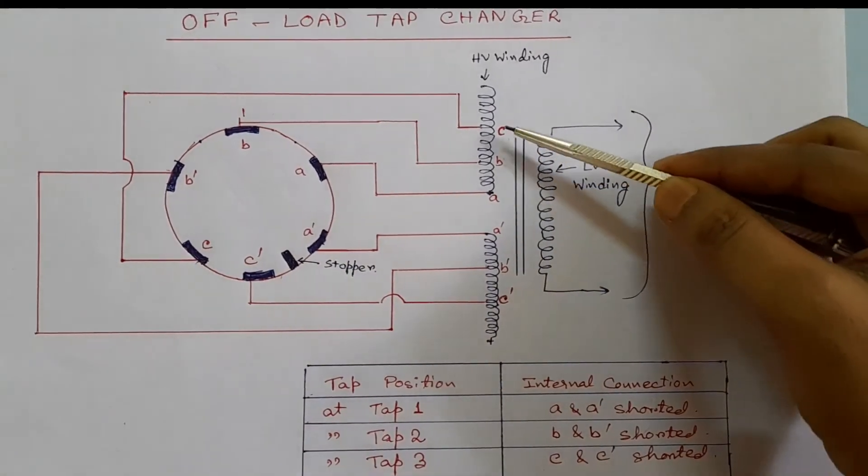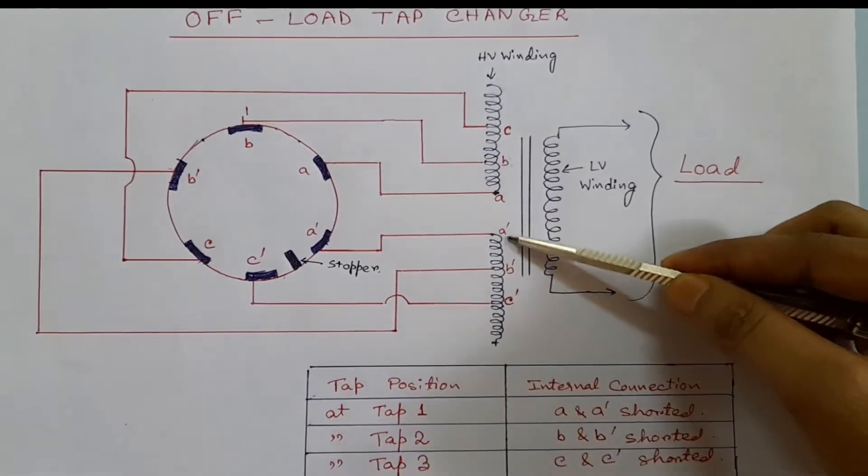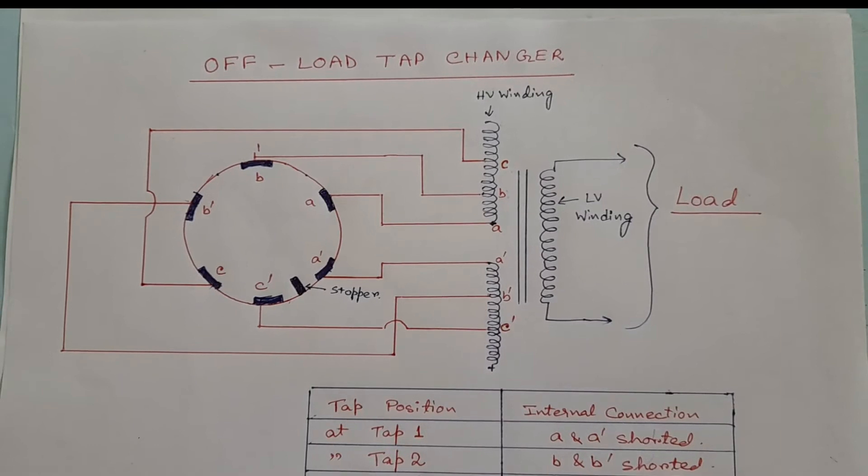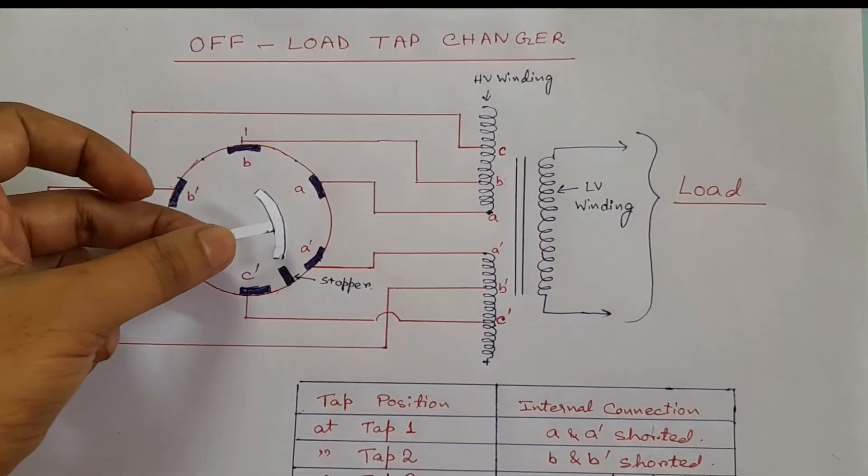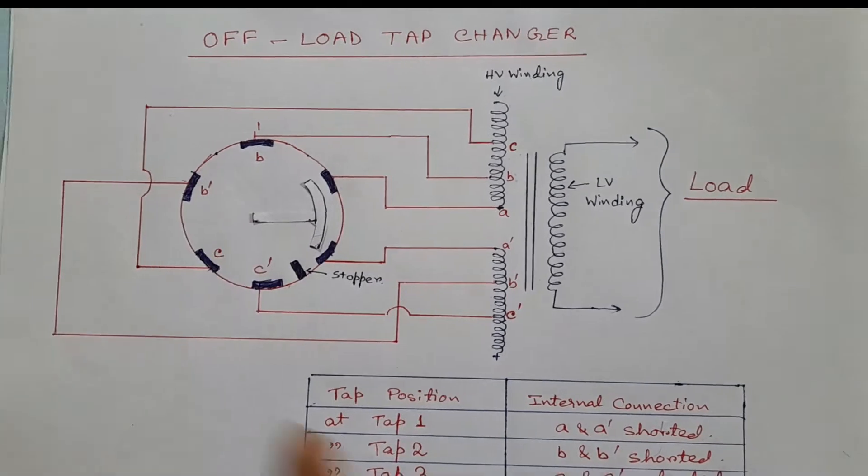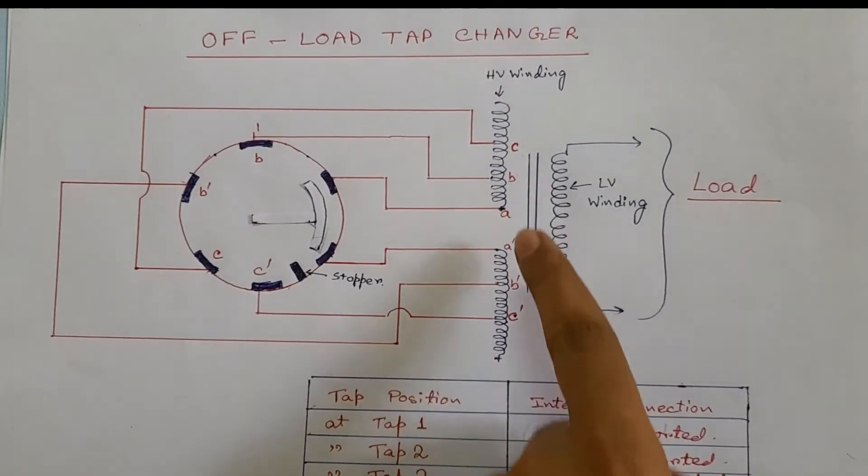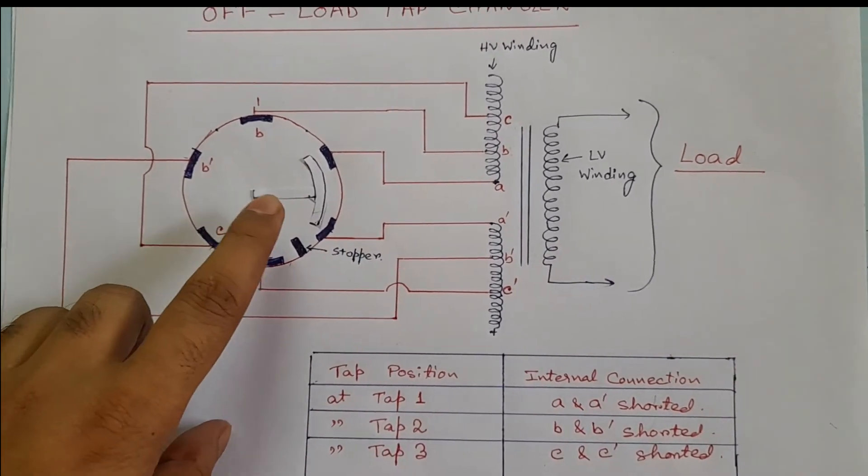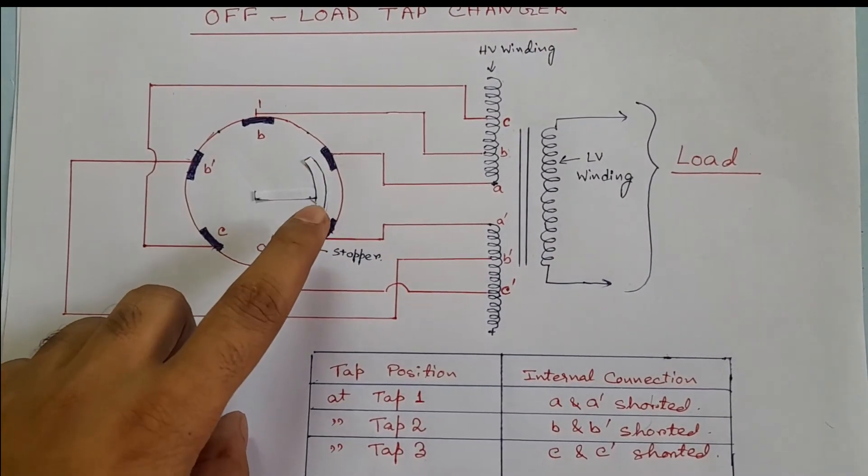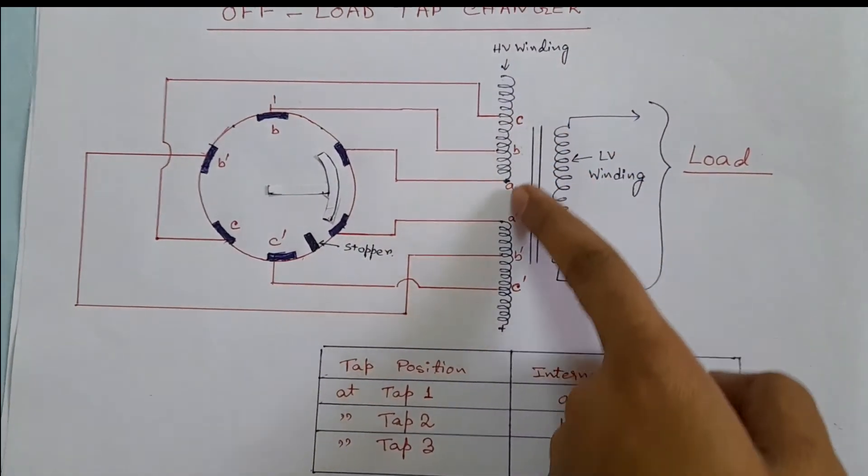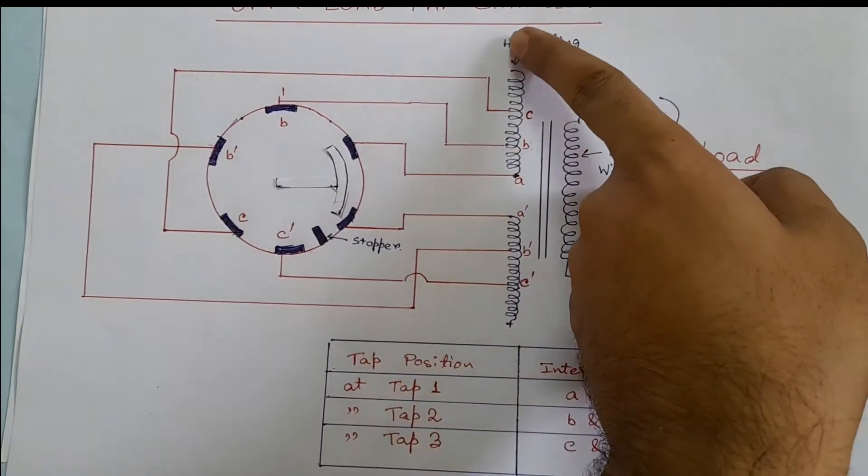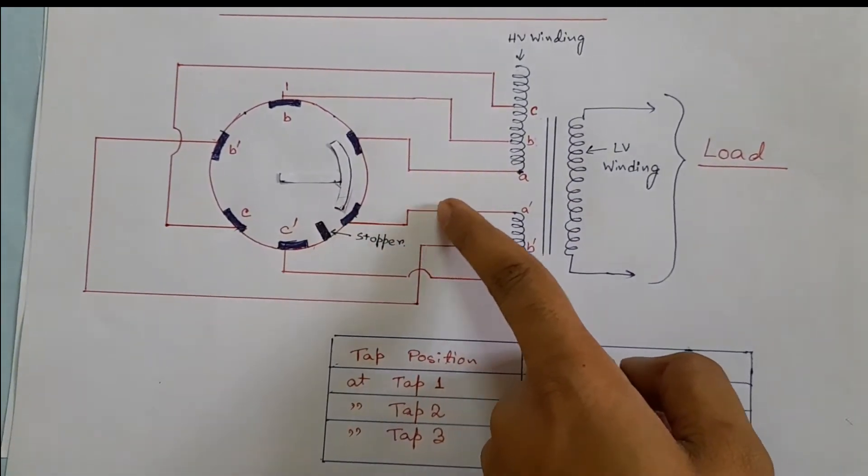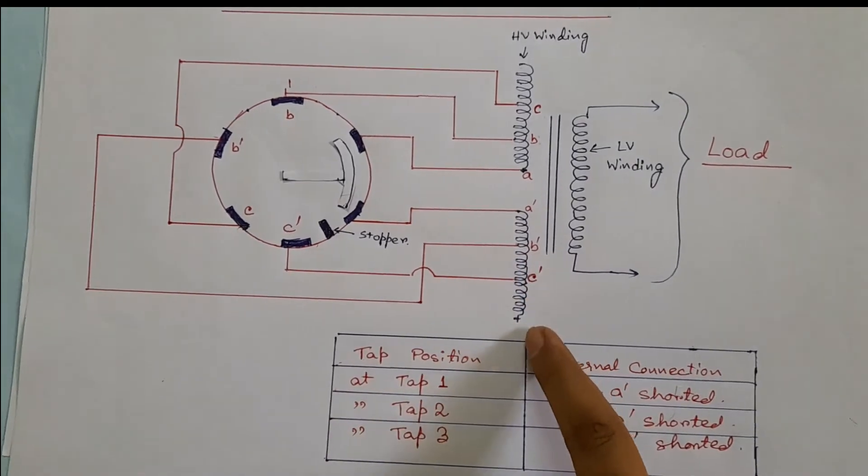As a result, there is no connectivity between the upper and lower side of the high voltage winding. But using a rotatable arm like this, we can easily establish connection between the upper and lower winding. At tap position one, this rotary switch is placed in this condition and the upper and lower windings are now connected. HV current will flow in this path. So this is a closed circuit and the connection is established.